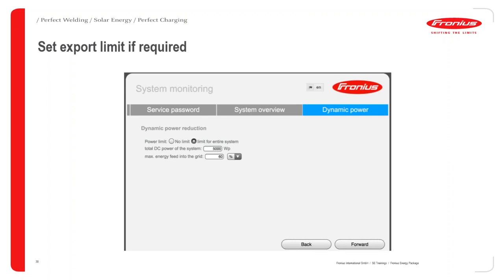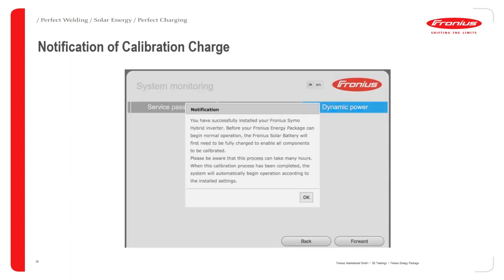The other thing there is your battery charging from other home producers in the network, deactivated or activated for that one. And then you go. The next step would be dynamic power. Dynamic power reduction is if you've got requirements from the network to have export limiting. So in this, if you don't have any export limits, then you just choose no limit. Otherwise, if you did, then you tick limit for entire system and then put in your total DC power of the size of the system.